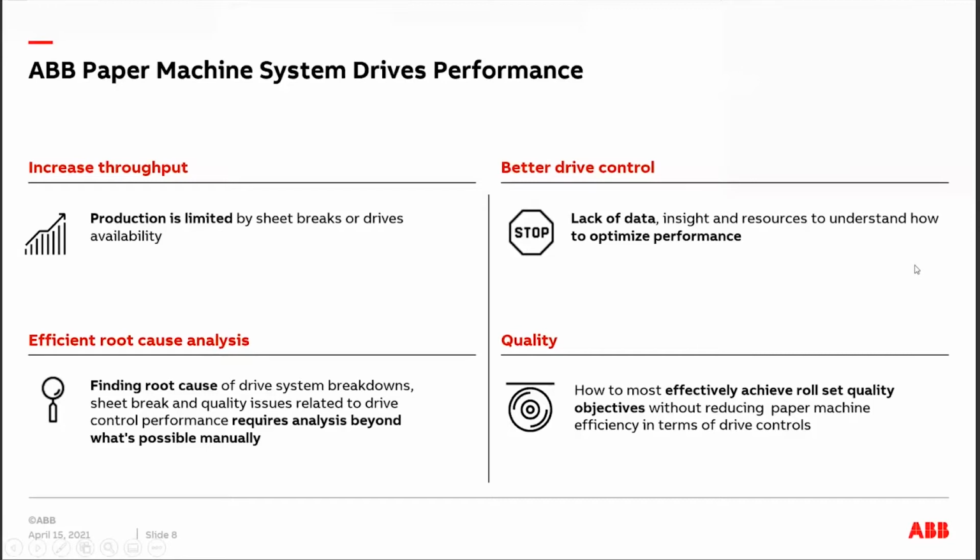And in order to do something like this, it really takes the ability to monitor down in the millisecond range in order to really determine if the controls are doing what they should be doing. And that's what the solution does. It collects information down at the millisecond range and performs online analytics of that millisecond information. And I'll talk about that a little bit too here in a few minutes.